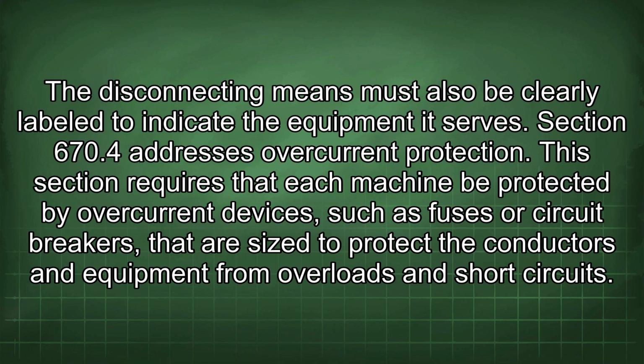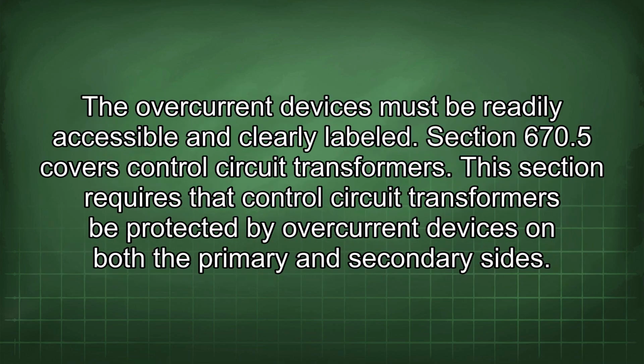Section 670.4 addresses overcurrent protection. This section requires that each machine be protected by overcurrent devices, such as fuses or circuit breakers, that are sized to protect the conductors and equipment from overloads and short circuits. The overcurrent devices must be readily accessible and clearly labeled.